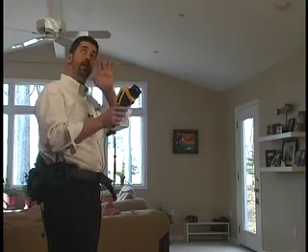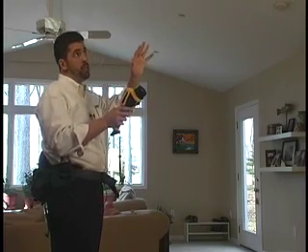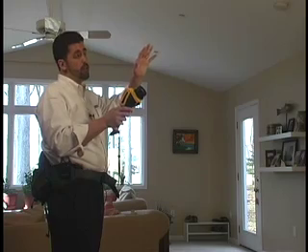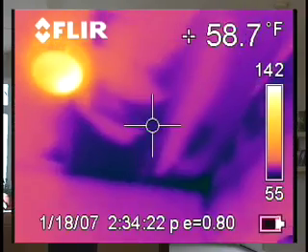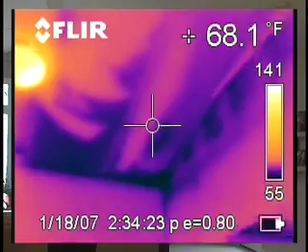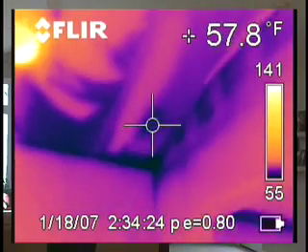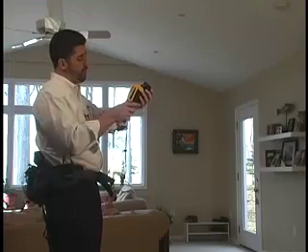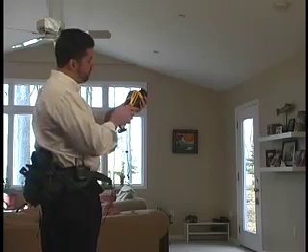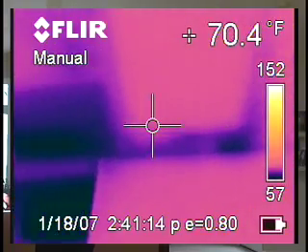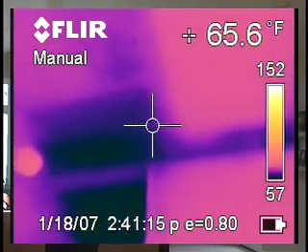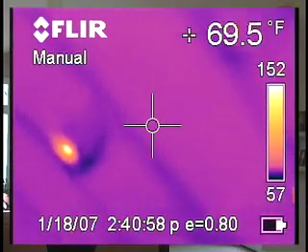We've scanned the inside gable wall, and I'm going to continue scanning from this corner. Even in this corner I see the same differences in temperature that we saw on the inside gable wall. As we continue our scan toward the exterior, I can see several places in the gable and in the ceiling that are areas of concern.